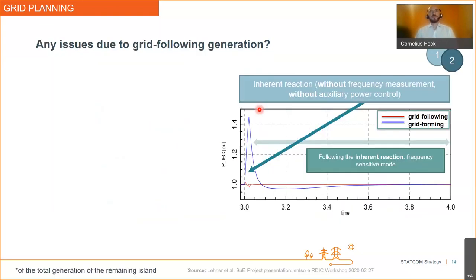I promise you a third issue that we are going to face in the next years. And this is the issue coming from power electronic interface generation, so especially from so-called grid following generation. I'm pretty sure most of you have heard the terms grid following and grid forming already, but what really is the difference?